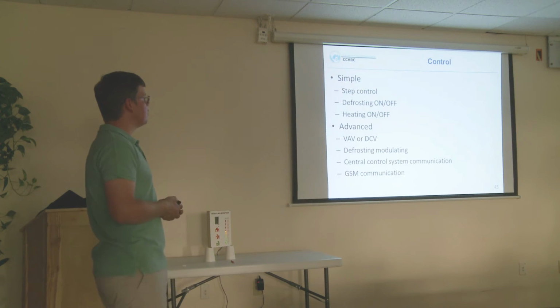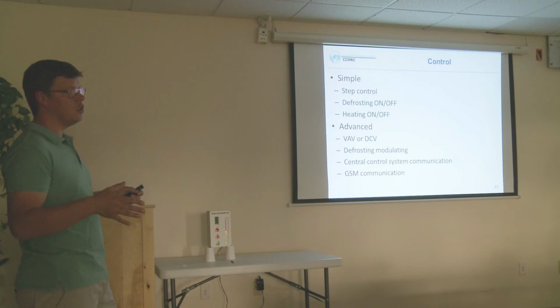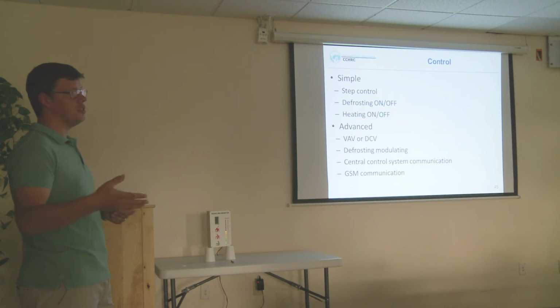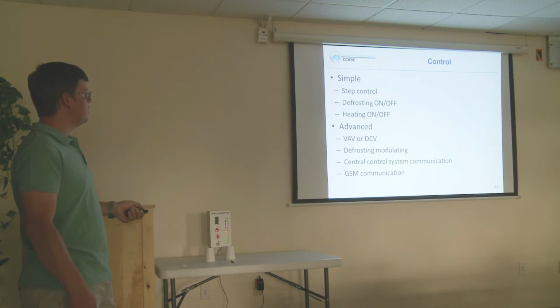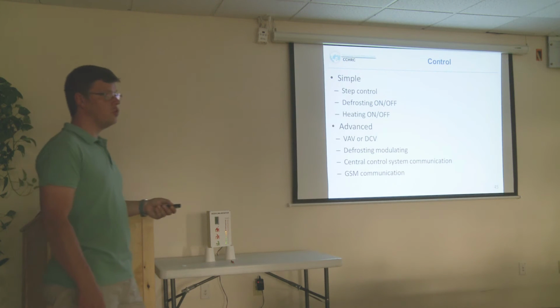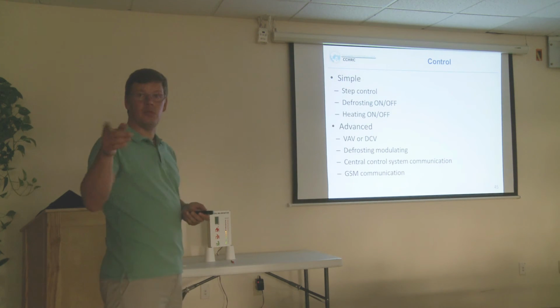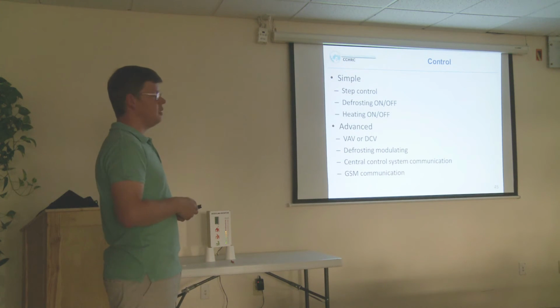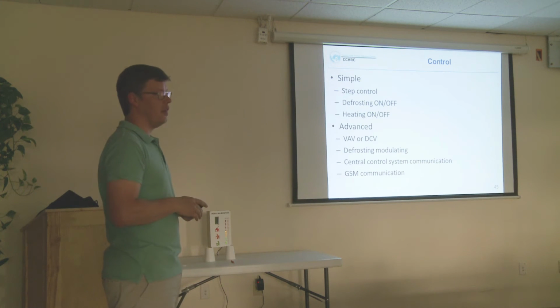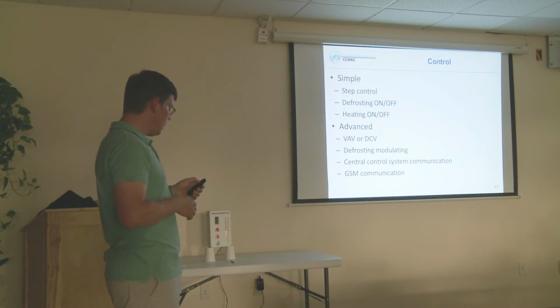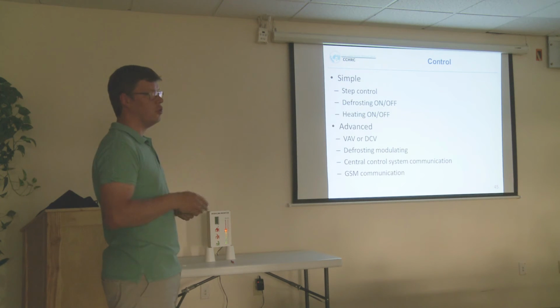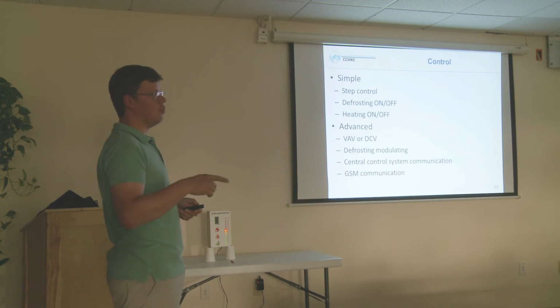On the other hand, the advanced controllers, even on these small domestic units, would already have some features which are common in the large HRVs or in the large industrial ventilation units, such as variable air volumes or demand control ventilation. That is what we have here. So we can hook up a CO2 sensor to the unit, and if the CO2 concentration goes up, the unit will speed up the fans to ventilate more. They could also modulate the defrosting function, so if it's 20 below, it will maybe speed up or slow down the exhaust fan a little bit. If it's 40 below, it will slow it down even more.